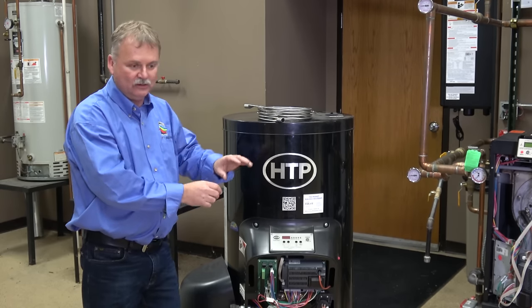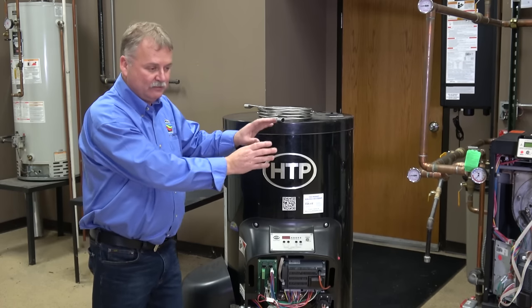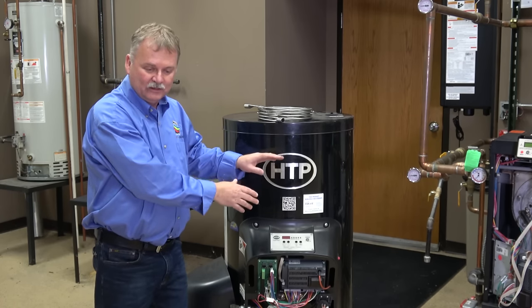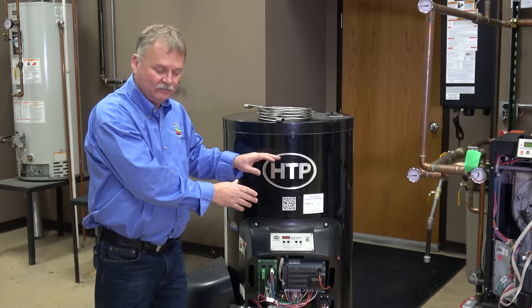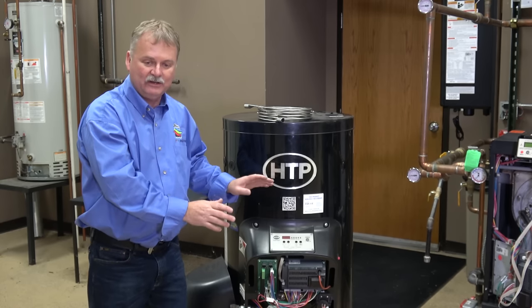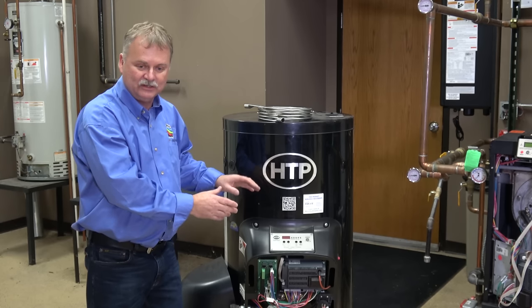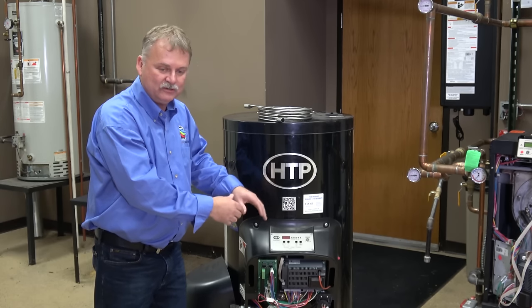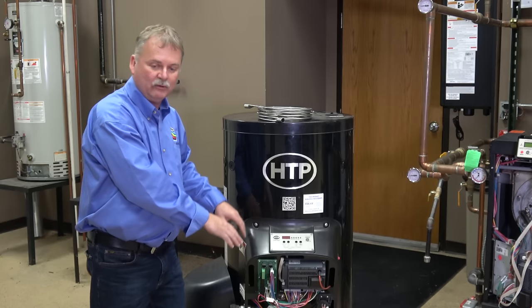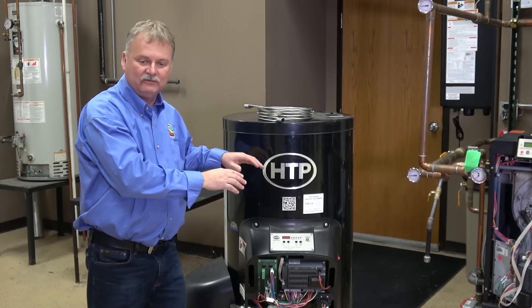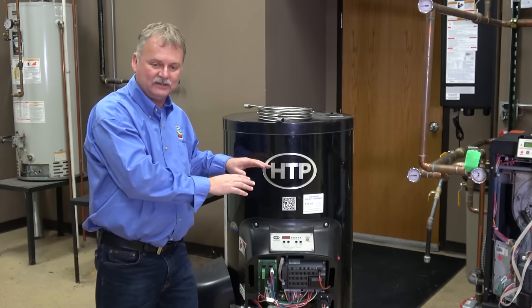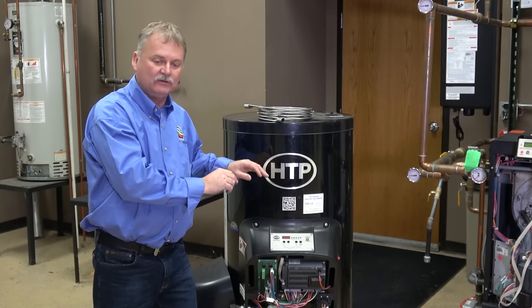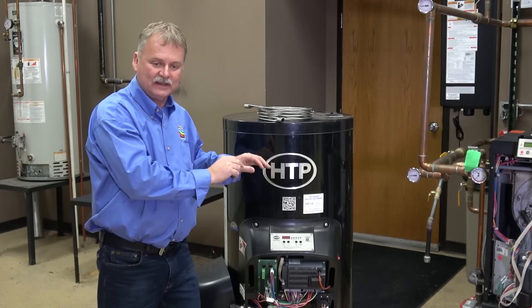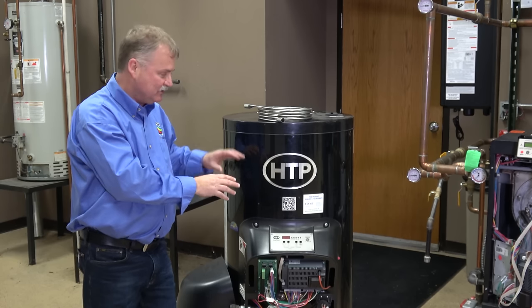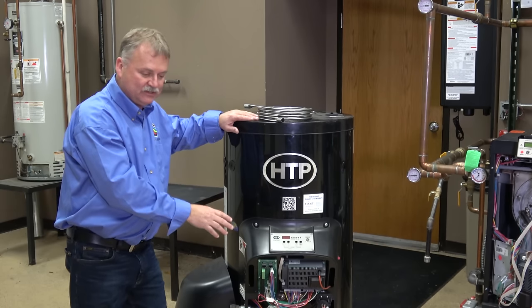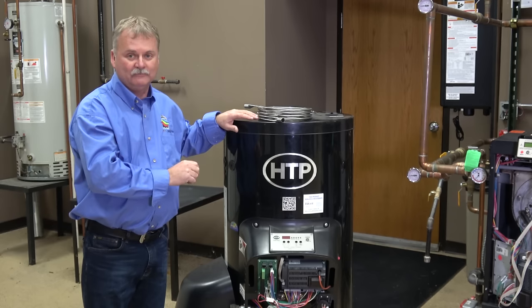Remember, we've got 55 gallons of BTUs of heat energy that we stored here. So a little zone here, a little zone there opens, takes those BTUs away, doesn't drop the tank temperature at all. The burner says, I don't need to fire. You didn't use any BTUs, you didn't use enough. Keep using BTUs until you bring it down low enough, then I will recharge. I'm going to run for 10 or 15 minutes or 20 minutes or whatever necessary, but I'm not going to click on for 20 seconds, off for 20 seconds, on for 20 seconds. So this is considered a high efficiency, high mass boiler.